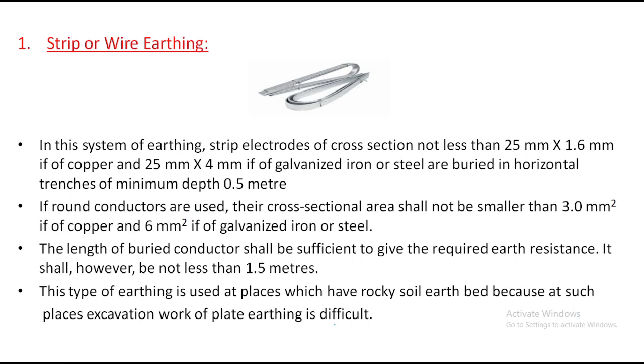Next. First, strip or wire earthing. Look, the earth wire looks like this. By that, the metal body is earthed. So here we have a metal body and we have a ground. In this system of earthing, strip electrodes of cross section not less than 25 mm by 1.6 mm are used. 25 mm is generally the width, and 1.6 mm is the thickness.